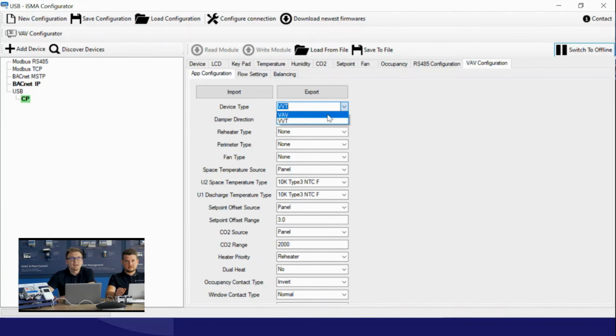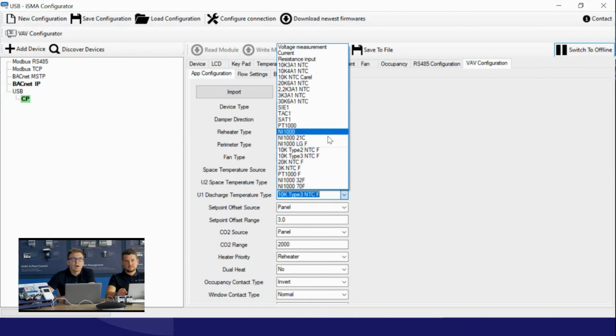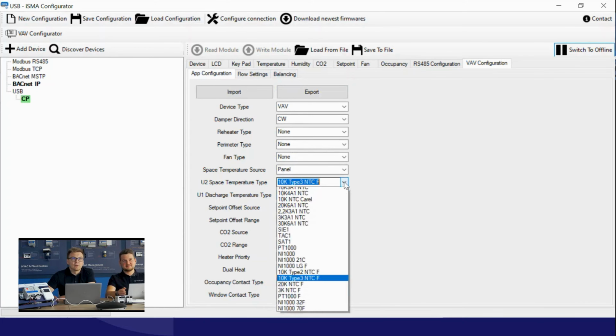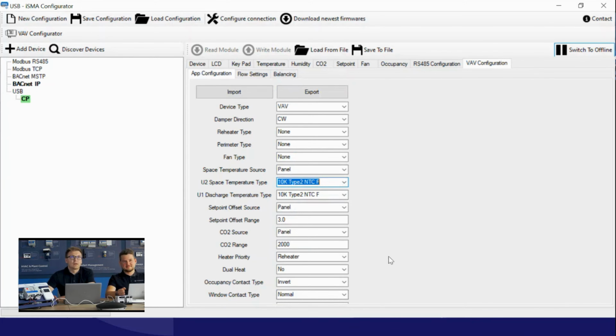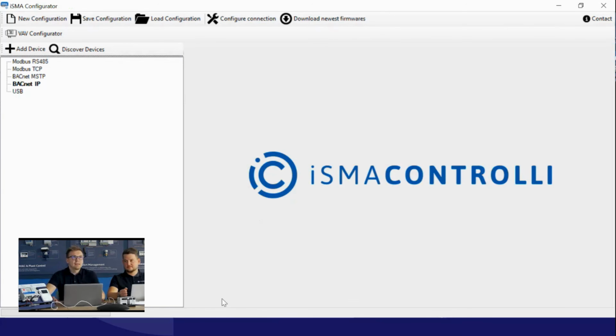And now I will make some changes using the USB connection. I will change the VAV type from VVT to VAV, and I will change the type of sensor connected to my VAV controller. I will choose type 2, the most popular, I guess. Type 2, exactly. Let's set type 2, the most popular in the United States. And I will just disconnect. So I will unplug my cable. You can see that the device disappears.